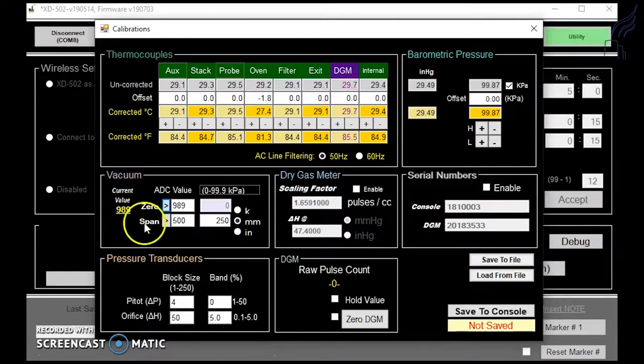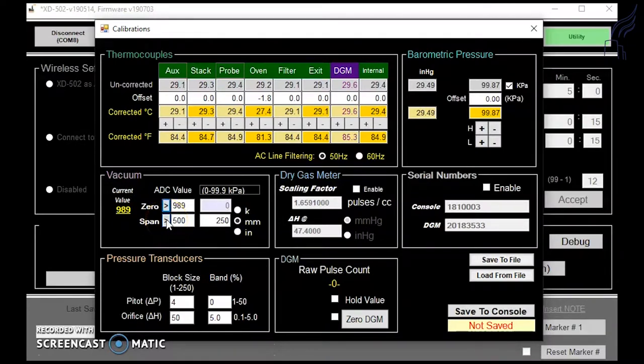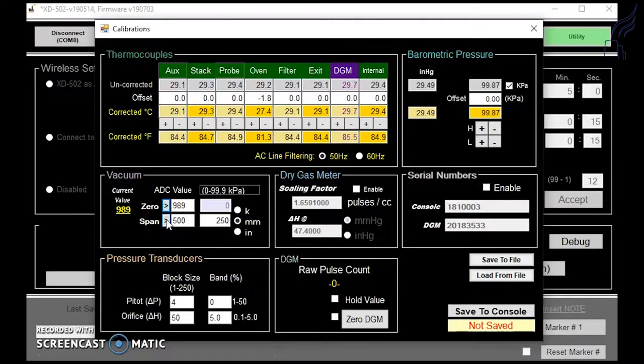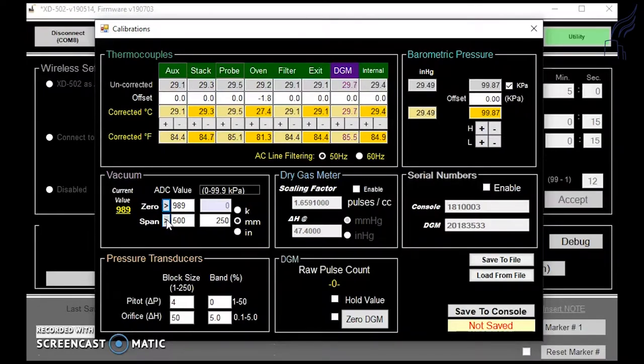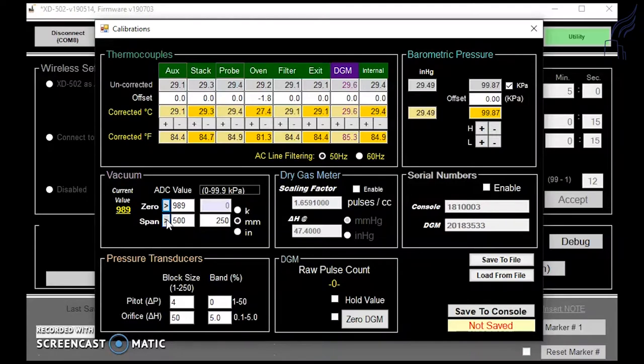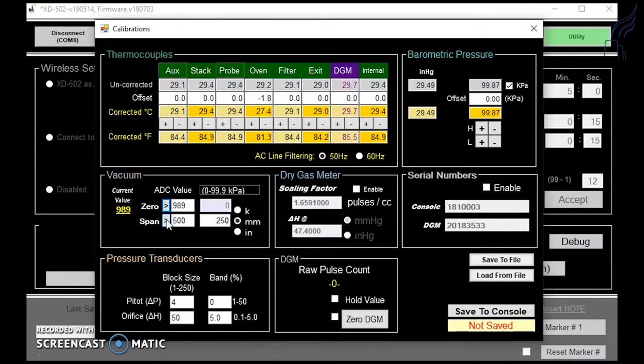To get your span, you'll need to insert your reference vacuum gauge into the half inch sample inlet on your console. You'll then turn on the pump and open up your valves to get the maximum amount of vacuum possible.